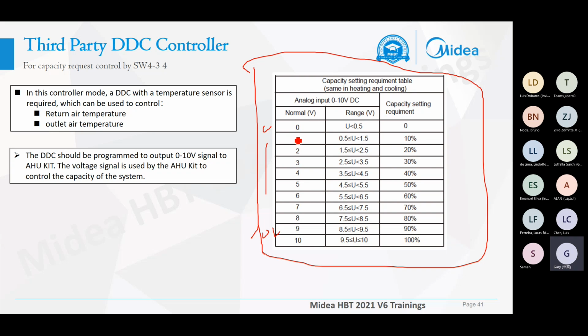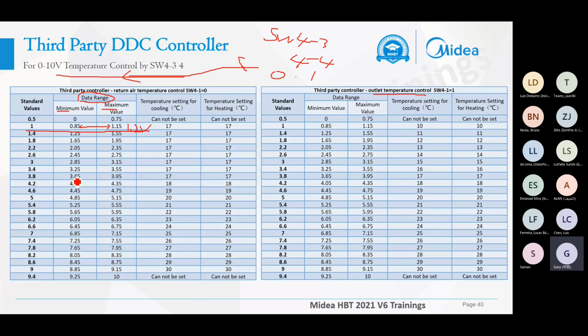For the capacity settings, you can find there is not any gap between the volts. It's the big difference with the temperature controls. In the temperature controls, they will have some gap between each standard value. So if you input a value in the gap, the controller will not have any response.